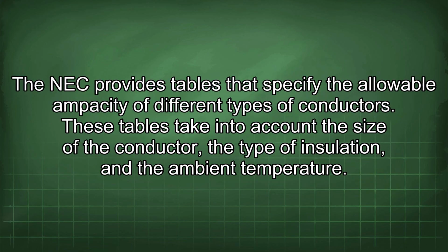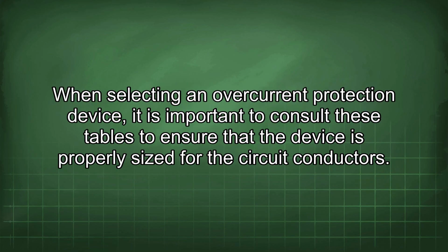The NEC provides tables that specify the allowable ampacity of different types of conductors. These tables take into account the size of the conductor, the type of insulation, and the ambient temperature. When selecting an overcurrent protection device, it is important to consult these tables to ensure that the device is properly sized for the circuit conductors.